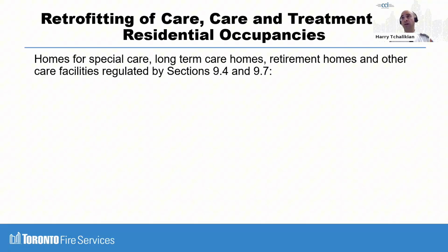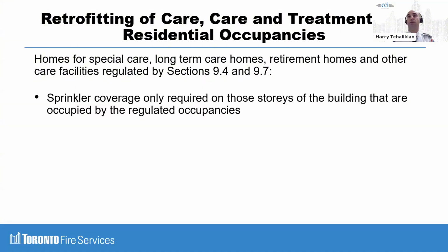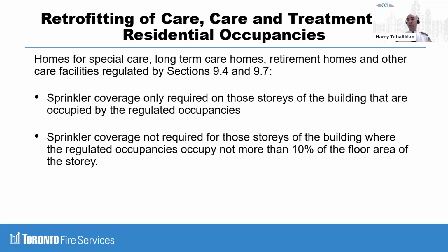Homes for special care, long-term care homes, retirement homes, and other care facilities regulated by sections 9.4 and 9.7. So now in the new fire code, sprinkler coverage is only required on those stories of the building that are occupied by regulated occupancies. Sprinkler coverage is not required for those stories where the regulated occupancies occupy not more than 10% of the floor area of the story. This is an absolutely massive relaxation.